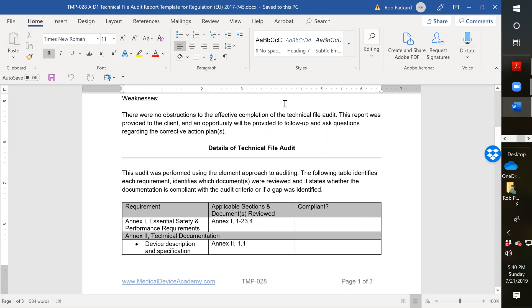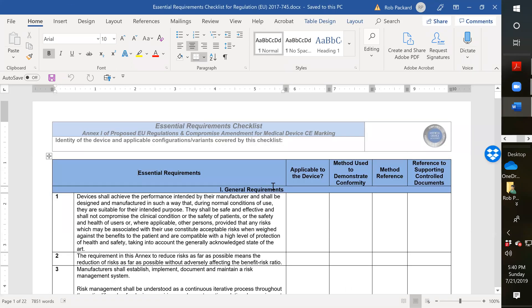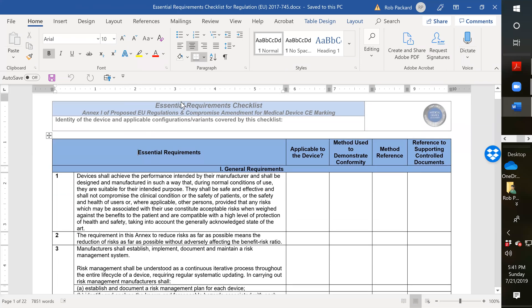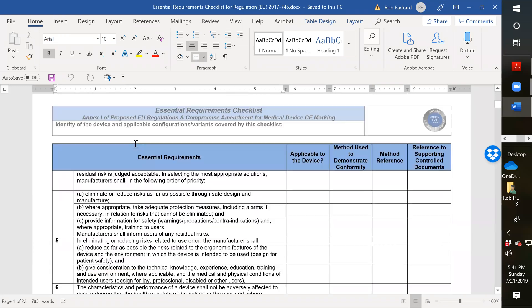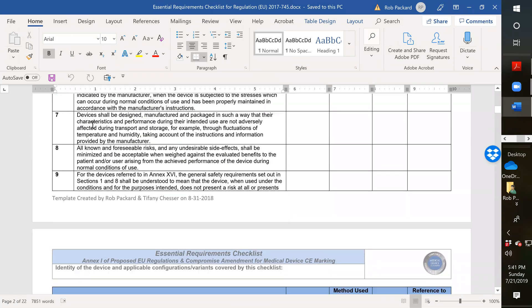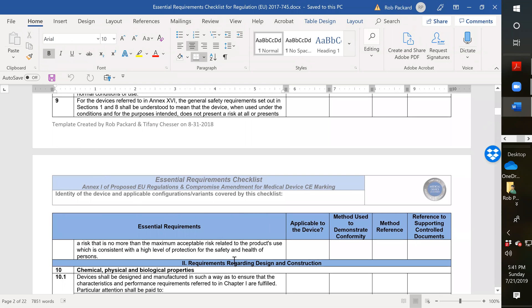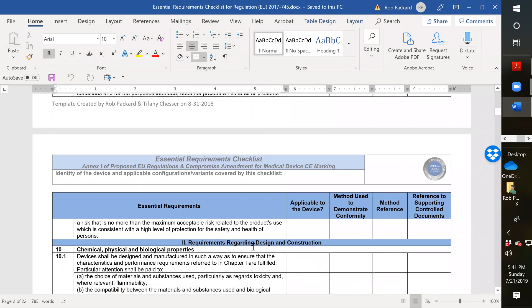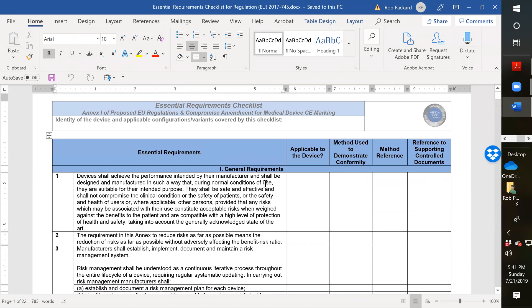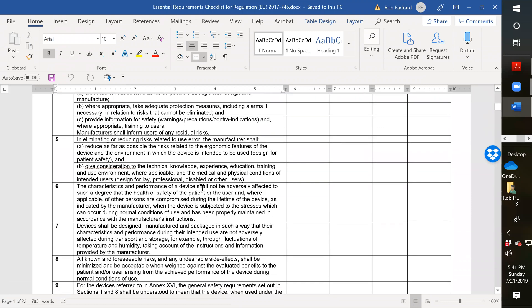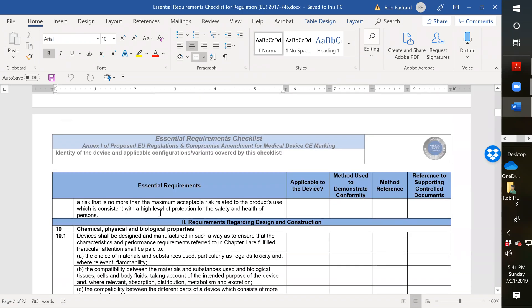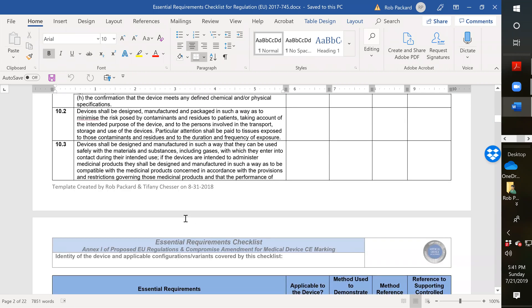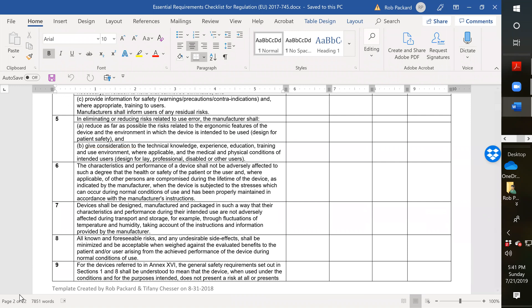If you're doing an audit of a company, you have to decide how deep you're going to go into this area. Do they have a template that's been updated? So I'll give you an example. When you look at the essential requirements checklist, this is one that's been updated to new regulations. That first section of general requirements stops at number nine. Then we go into requirements regarding design and construction. At the top here, you'll see it's general requirements, items one through nine. Then item 10 gets into the specific design and construction. It goes all the way down to 23.4, and you can see it's pretty long, a 22 page template.